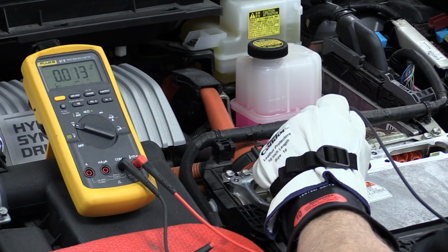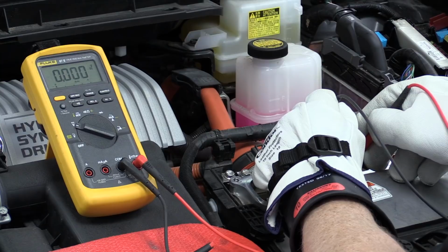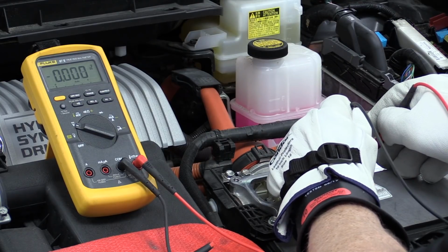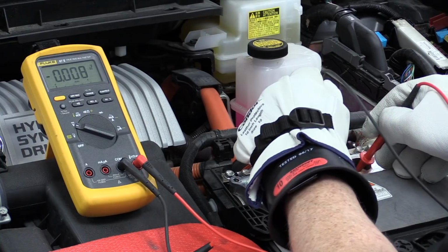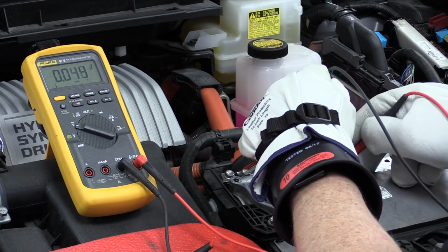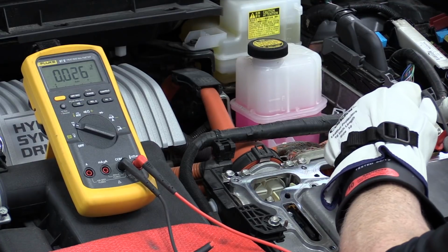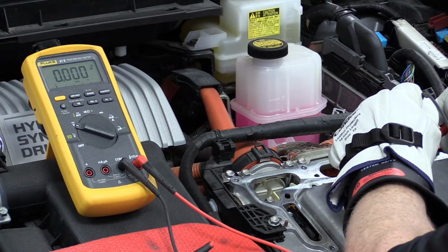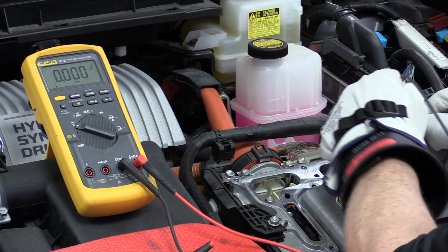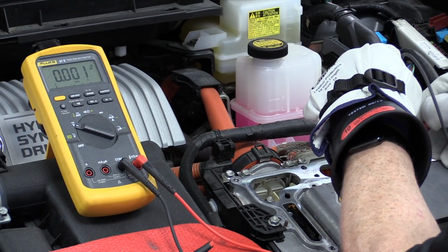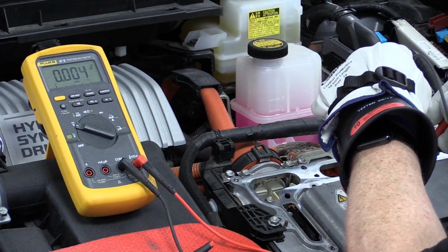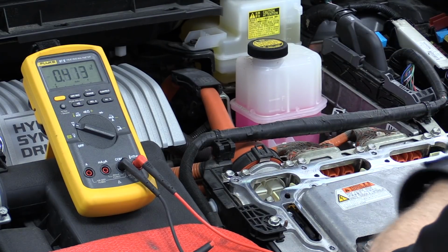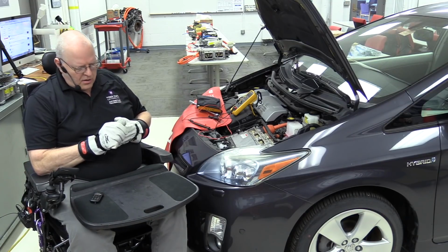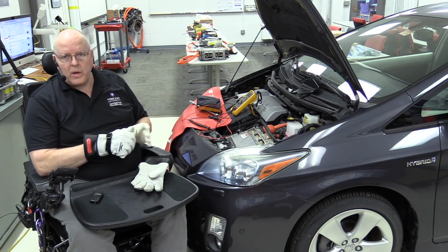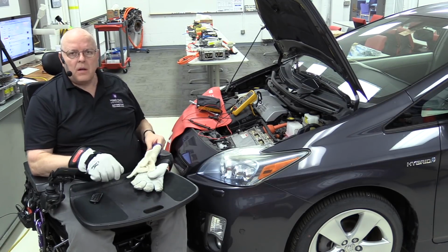So we're just going to check on DC. We'll go from each terminal to terminal: 0, 0, 0. Each terminal to the case: 0, 0, 0. Same thing on the other. Two outsides together, inside to outside, inside to outside, outside to case, middle to case, outside to case. They're all 0, so there is no dangerous voltage on these terminals.